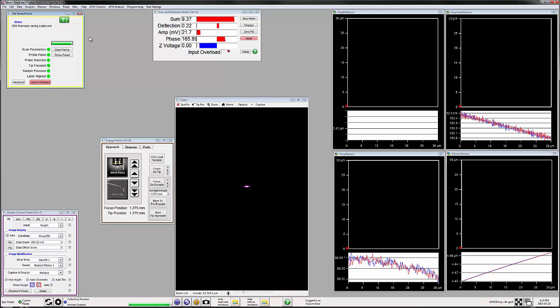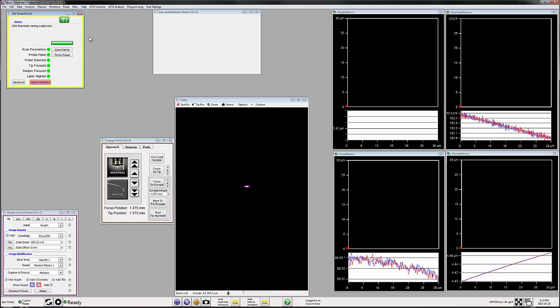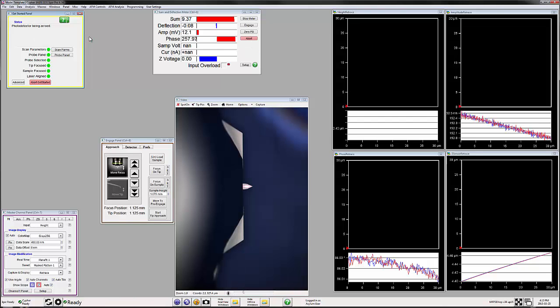Once the thermal is done, the next thing that happens is an auto-tune. This finds the resonant frequency of the cantilever. Know that we're doing this pretty far away from the surface, which means that we're less influenced by different air layers or squeeze films on the surface. Once we engage, we'll do another auto-tune very close to the surface in order to take these effects into account.